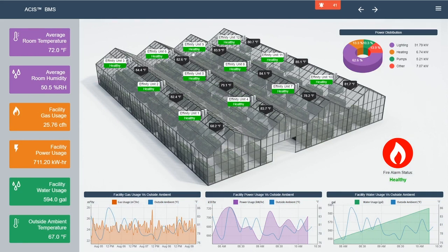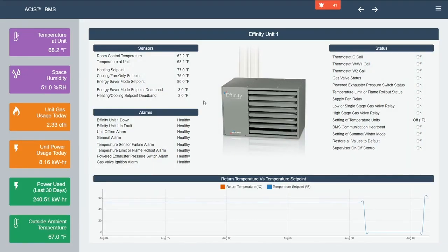If you connect into one through this interface, we now get all of this information. We get all of these sensor values, which is the room temperature, the temperature at the back of the unit, which is actually used for the energy saver mode as well. So built into this board we also get the energy saver function. If the temperature up in the ceiling void where the unit is high enough but we still have a heating call from the space, we can just run the fan to destratify the air down to the floor, which means that you don't actually need to run your gas burner, which obviously is an energy saving function.